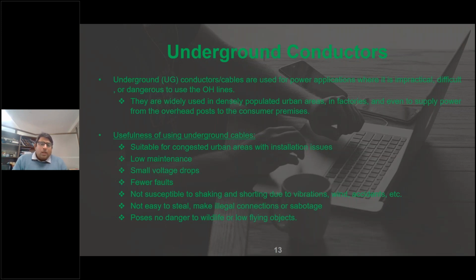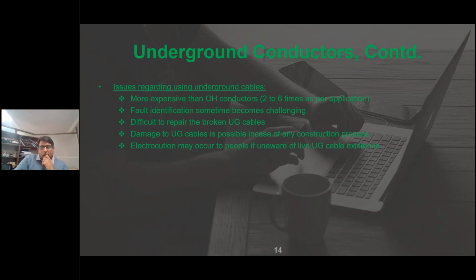The issues regarding these underground cables are that, because science does not solve any problem without creating ten, they are more expensive than overhead counterparts. It may go from 2 times to 6 times as per the application for which you are installing them. Fault identification sometimes becomes challenging, and if some fault happens, it is difficult to repair the broken underground cable. Damage to underground cable is possible during any construction process, and electrocution may occur to people who are unaware of the underground cable's existence. So they usually put up signs that there are underground high voltage or medium voltage cables going through this point.